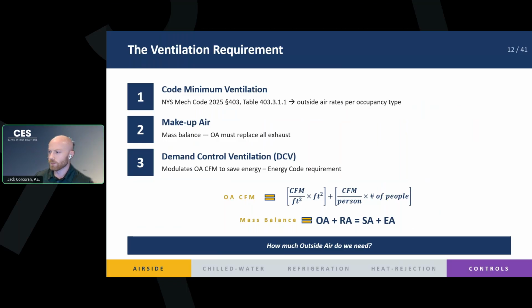So the ventilation requirement, right? How do we know how much outside air? Every project requires outside air per code. It is in the New York State Mechanical Code or New York City Mechanical Code, all derived from the International Mechanical Code. But there's a table in Chapter 4 that has all the outside air rates per occupancy type. So basically, you're delivering a certain amount of CFM per square foot and then a certain CFM per person in the occupied space.